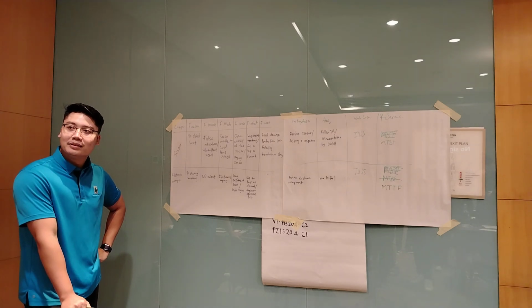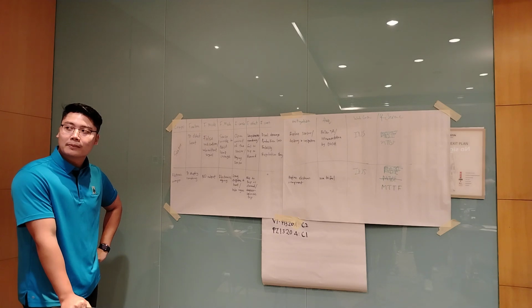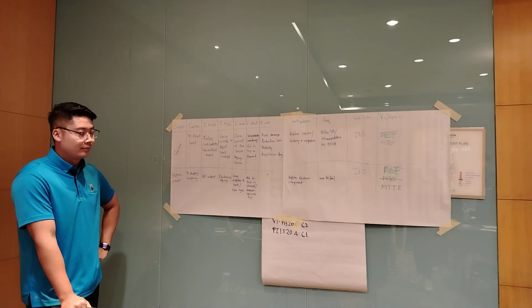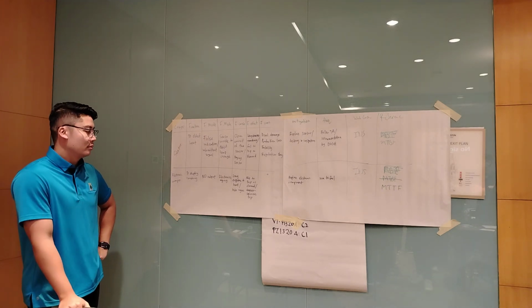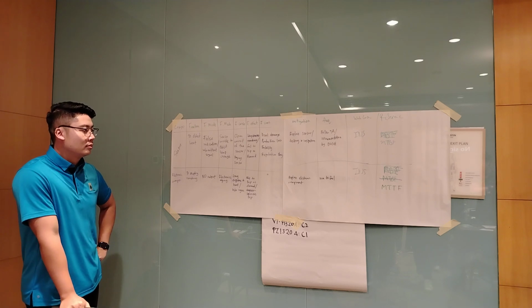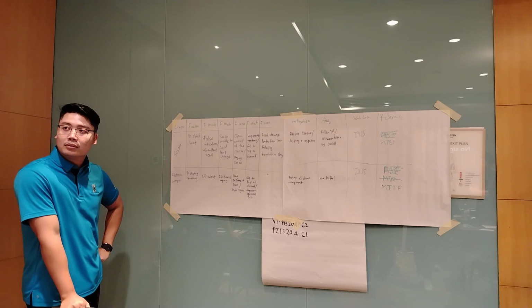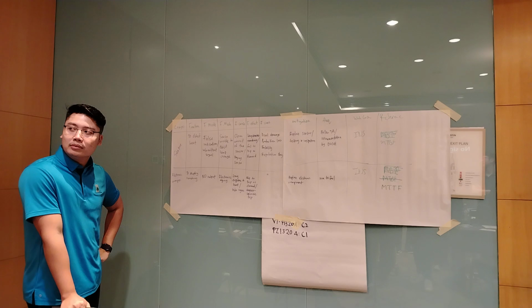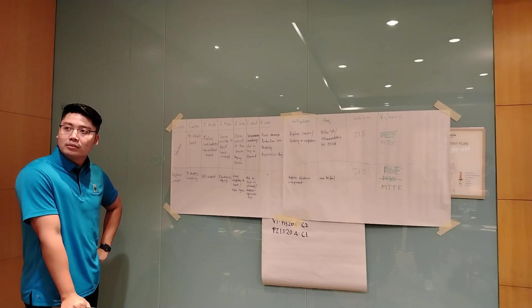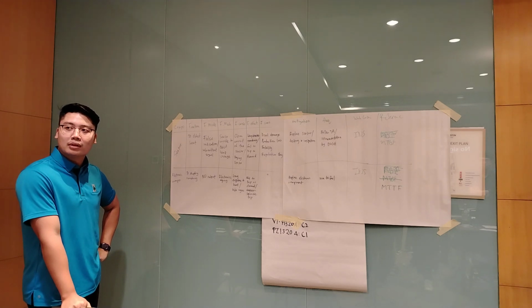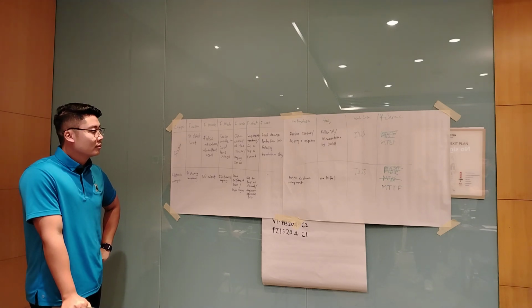Usually kan, in instrumentation design, we usually have redundancy. So once this electronic component fails, it's only one of the heat detector as one function. We still have another function, and we also have our voting system, right? So it will not trip lah actually. I think the consequences only happen kalau benda tu ada api betul-betul.